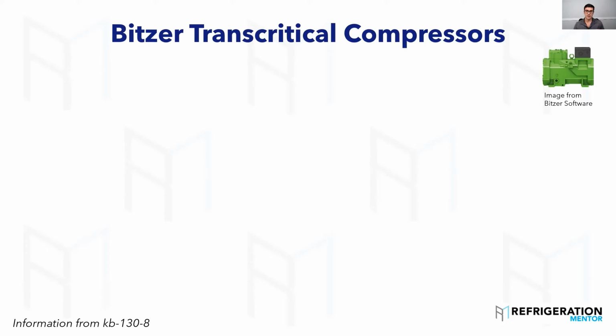Okay, so this information is out of the KB130. There's two different types of oils they recommend. So the BSG 68 for cascade systems. And what a cascade system is, you'll have one refrigerant on top, we'll say 448 on the top, or ammonia, or propane, whatever it is on the top. And then on the subcritical side would be your CO2.